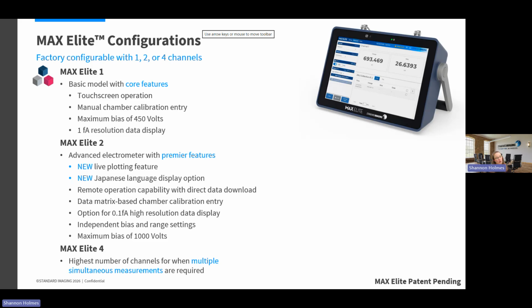The 2 channel has that remote operation capability, and we've added direct data download. That's something that I wanted to get in there as soon as we could, so that if you're operating it from your computer, you can download your CSV data file directly to your computer. It has the camera for the data matrix based chamber calibration entry. Usually it's people in Japan who are asking for the very high resolution data display, but for those outside of that country as well who want extremely high resolution on the data, we do offer the 10th of a femtoamp resolution. The two channels have independent bias and independent range settings, so you're not stuck needing to have matched type chambers or matched signals when you're measuring with both channels.